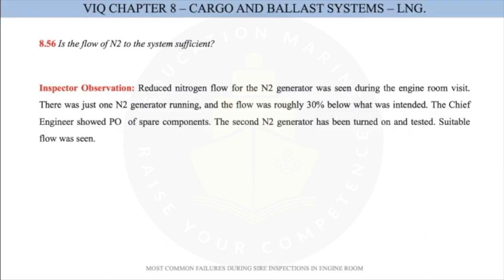The flow was reduced most probably because of the membranes. So the membranes, with time, get older, they wear out, and they reduce the flow. Most probably it was because of this. It was an observation. So you see, luckily the chief engineer had the spare parts order, so he showed that the order was placed, and he asked to test the second nitrogen generator, which was on standby, and it luckily showed good performance.